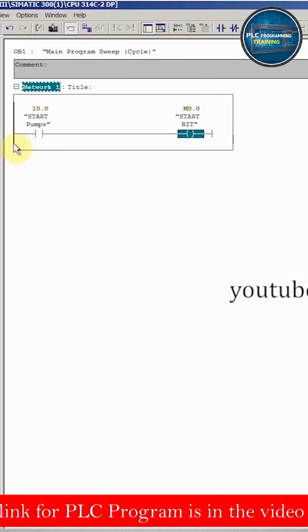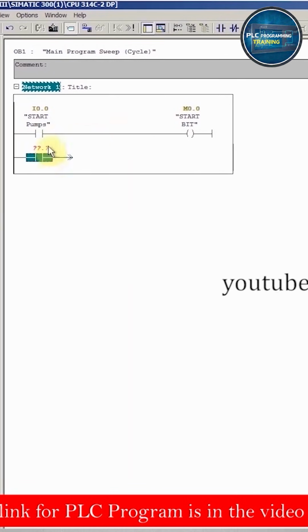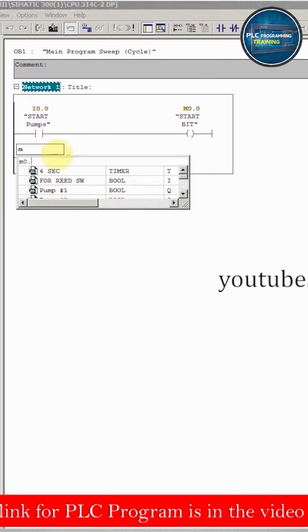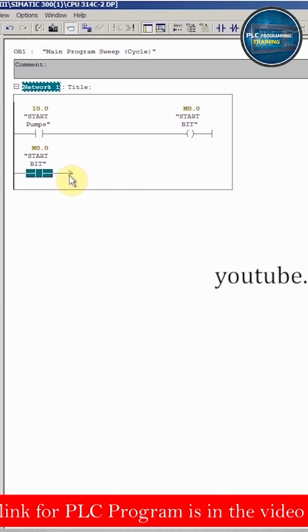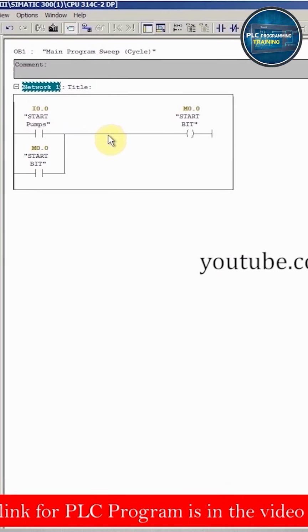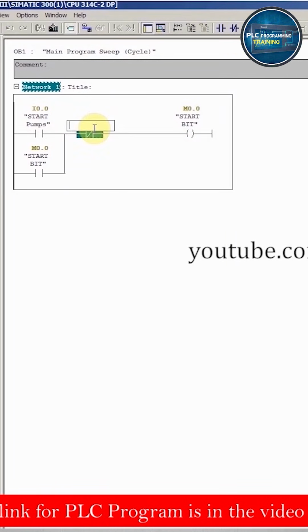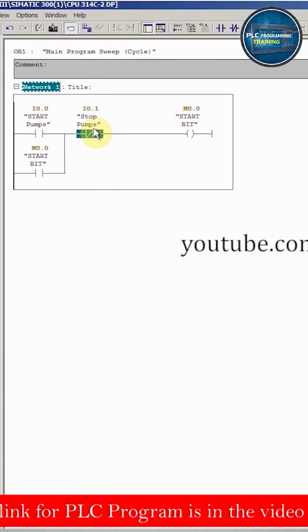To hold on, we will simply insert a branch here, a NO contact, assign it the same M0.0 and connect the branch here. So whenever the start bit is on, it will get power through its own NO contact. Now to turn off this start bit, we will use the stop push button. So we will insert an NC contact here and we will assign it I0.1, which is our stop push button.